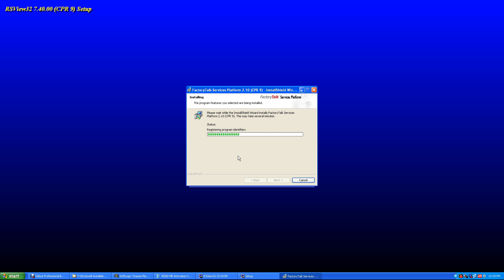I'm going to try to install FactoryTalk View — that's what everybody's using today. This is an older version, it's version 5, and it has a problem installing with .NET 2. Allen-Bradley came up with a workaround where you take registry files and merge them with the registry. One is to install it, and when you're done it thinks it's version 2.0; then you hit the other file, merge it back, and it puts things back where they were. It says 'remove after installation.' It's not complex — it's pretty handy, powerful, and simple to use.